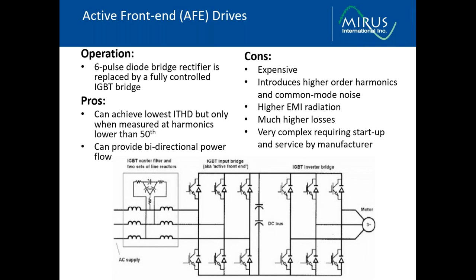Their main benefit and application is in the ability to convert power bidirectionally. So if you have an application where you can generate power from the load and feed it back into the power system, then the AFE drive is a good solution. But I would suggest that if the only reason we're putting an AFE drive in is for treatment of harmonics, then there are much better choices than an AFE drive. This is because the AFE is very expensive, but it also introduces higher order harmonics and common mode noise. It introduces EMI radiation, has higher losses, and is quite a complex device and requires startup and service by the manufacturer.